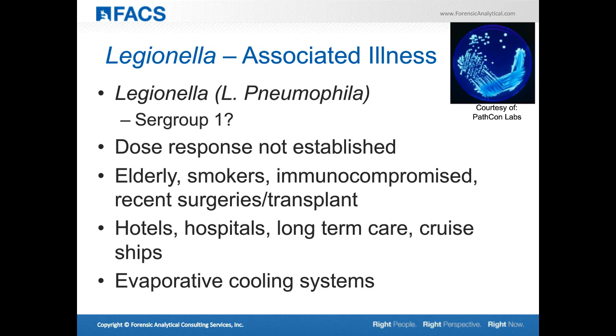In terms of growth conditions, we look at the source of the water. If it comes from a natural source like a lake, or has a high organic or sediment load, that can lead to growth conditions for Legionella because there's more food available for it to grow. Low water flow or stagnant water is associated with Legionella growth. Legionella grows really well typically between 95 and about 120 degrees, with a wide growth range between 80 and 120, and we even see growth outside that range, though that's typically the most susceptible area.